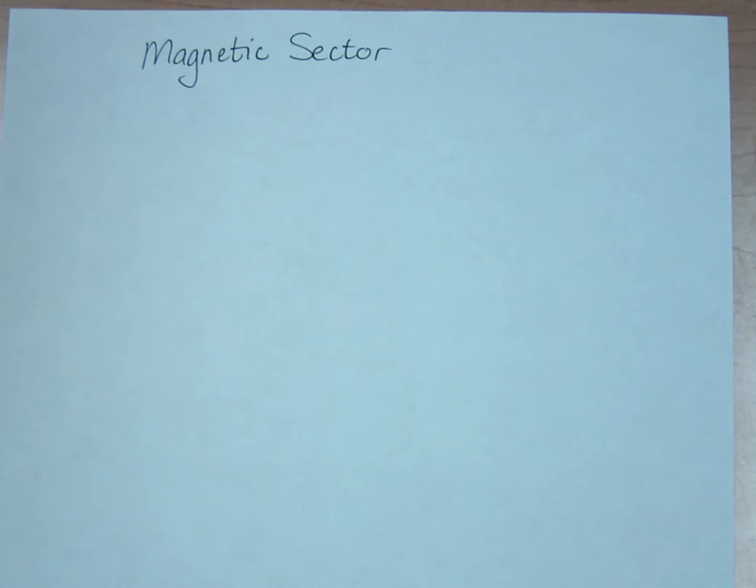Turning our attention to mass analyzers, which have the purpose of separating the ions that have been formed to detect each of the individual mass to charge ratios. There are three main ones that we'll cover in this course. The first of which is the magnetic sector, which is the oldest of the three different types, and probably the one that is least used now, but it's a good foundation for looking at how ions move and how we can control their movement by their mass to charge ratio. We'll have later videos for the quadrupole and the time of flight that show the basics of how those work.